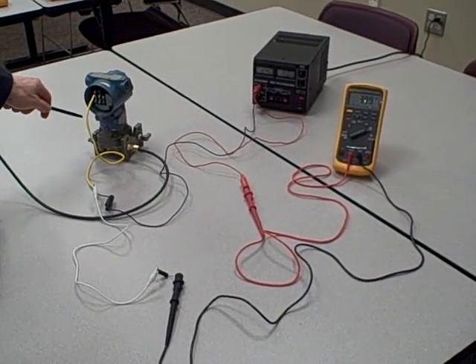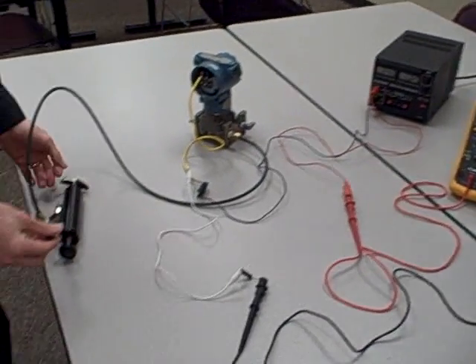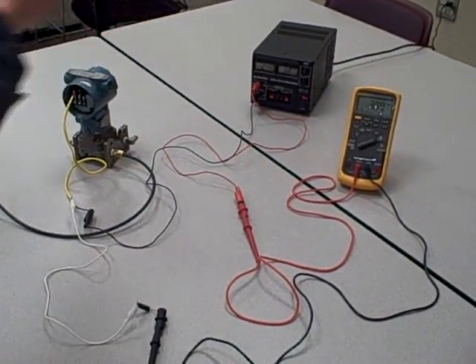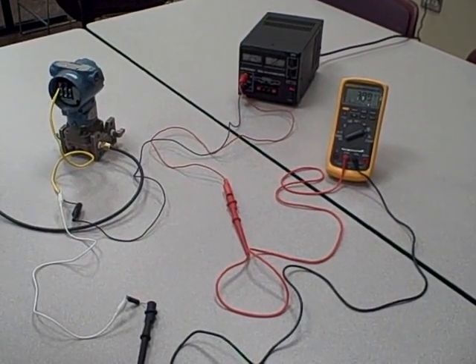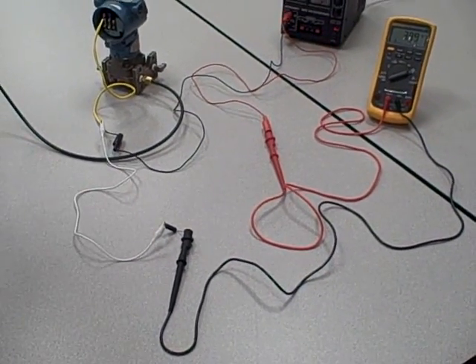Here we have a Rosemount Model 3051 differential pressure transmitter connected to a hand pump where we can apply air pressure. We have this transmitter powered by a 24 volt power supply. We're measuring the current using a Fluke 87-4 meter and we also have the current going through a 250 ohm resistor.